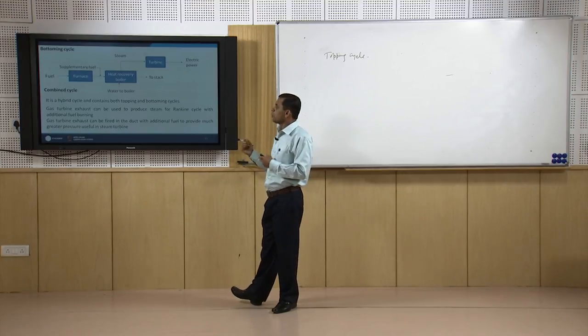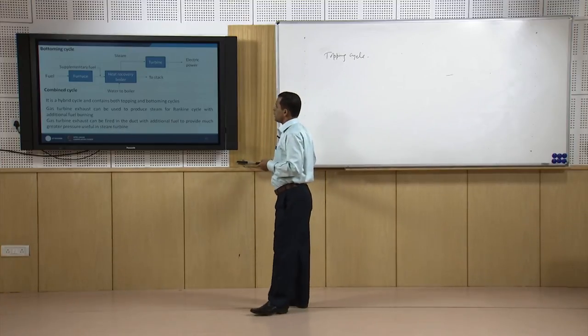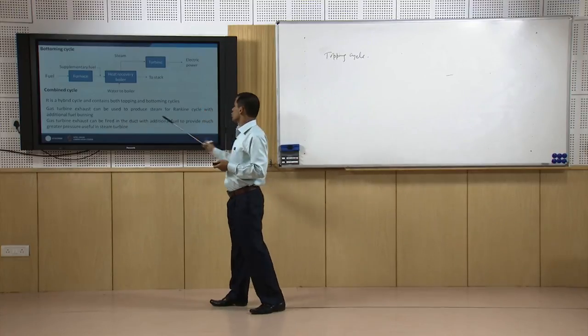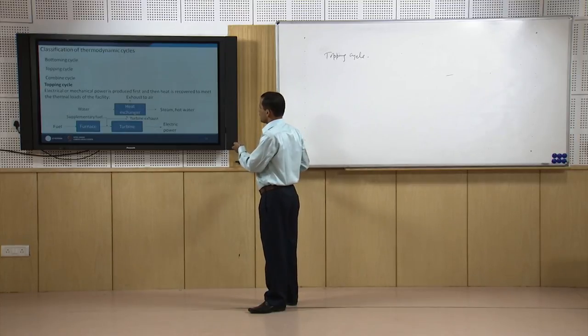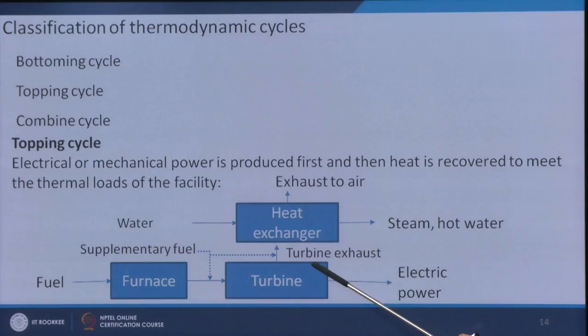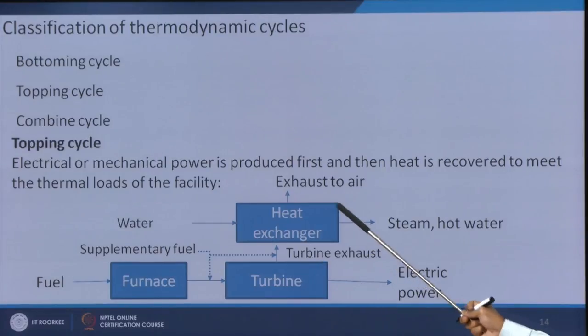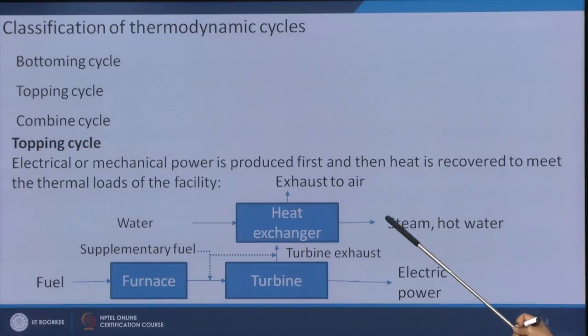The combined cycle means both topping and bottoming cycles are used simultaneously. Gas turbine exhaust can be used to produce steam for a Rankine cycle with additional fuel burning. In the first case, the turbine exhaust goes and we produce steam or hot water. If instead we use that steam for electricity production using a steam turbine again, then this is called a combined cycle.